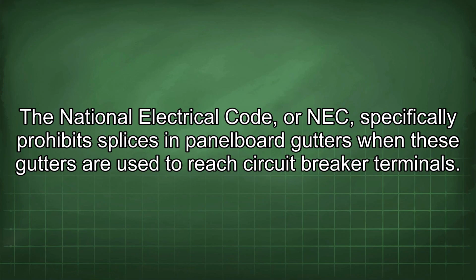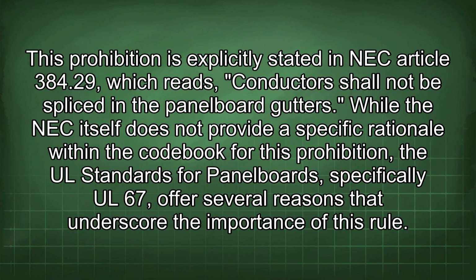The National Electrical Code, or NEC, specifically prohibits splices in panelboard gutters when these gutters are used to reach circuit breaker terminals. This prohibition is explicitly stated in NEC Article 384.29, which reads, "Conductors shall not be spliced in the panelboard gutters." While the NEC itself does not provide a specific rationale within the codebook for this prohibition, the UL standards for panelboards, specifically UL 67, offer several reasons that underscore the importance of this rule.